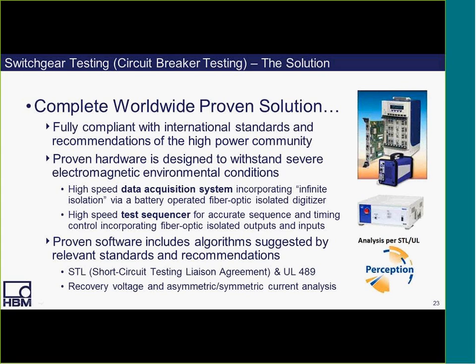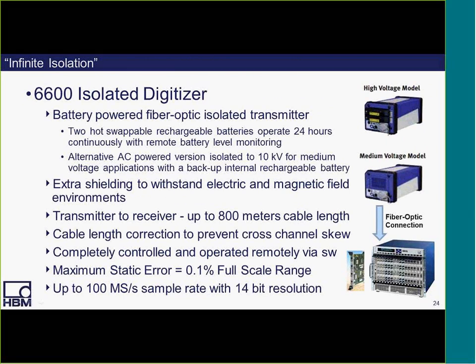And there's also proven software that includes algorithms suggested by relevant standards and recommendations, including STL, the Short Circuit Testing Liaison Agreement, and UL489. So you can make analysis measurements such as recovery voltage and asymmetric-symmetric current analysis. Starting with the hardware, the 6600 isolated digitizer provides infinite isolation using a battery-powered fiber-optic isolated transmitter, which does have two hot-swappable, rechargeable batteries that provide up to 24 hours of continuous operation and remote battery-level monitoring.